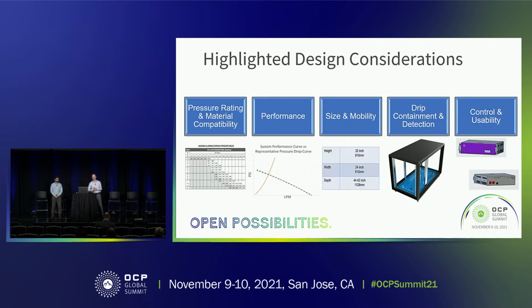So now with the remaining time left, I just want to hit on some of the key design considerations and maybe some of the trade-offs that need to be considered when designing a cart like this for the data center. First of all, and I'm sure you've heard it in a lot of other talks, material compatibility and pressure rating for every component is absolutely crucial to understand. Every component must meet or exceed whatever pressure rating for the fluid system that this cart is going to be used with. Additionally, for material compatibility, there should not be any concerns about corrosion or contaminants or any sort of adverse reaction between the cooling fluid and the materials used within the cart components.